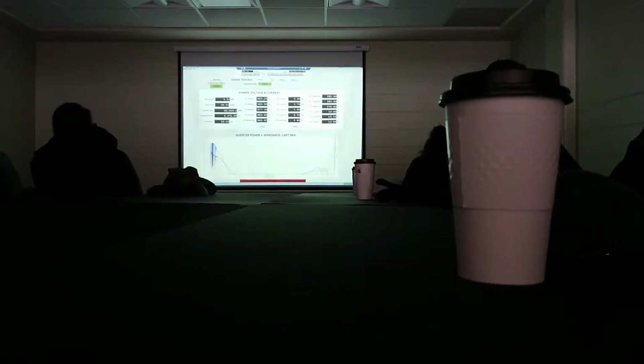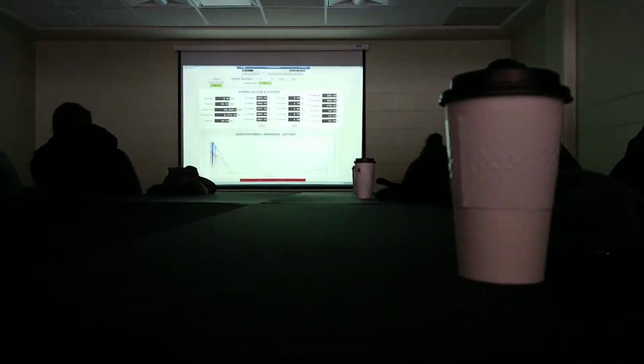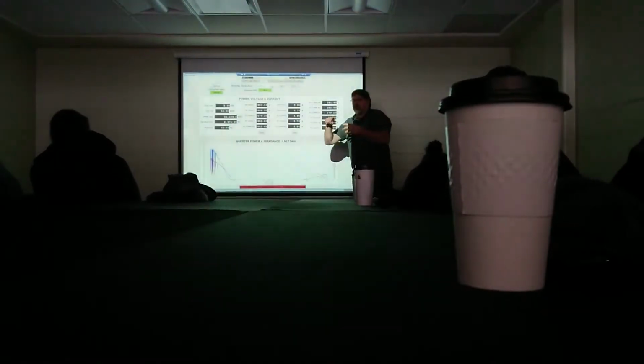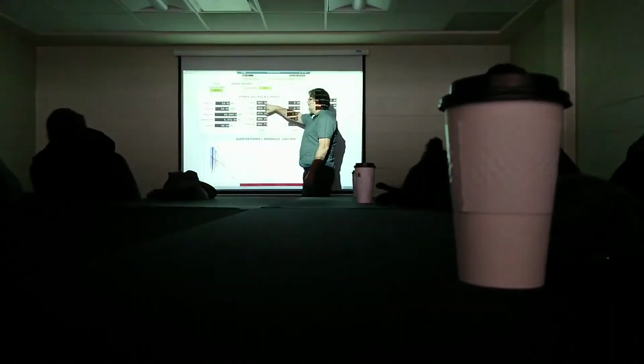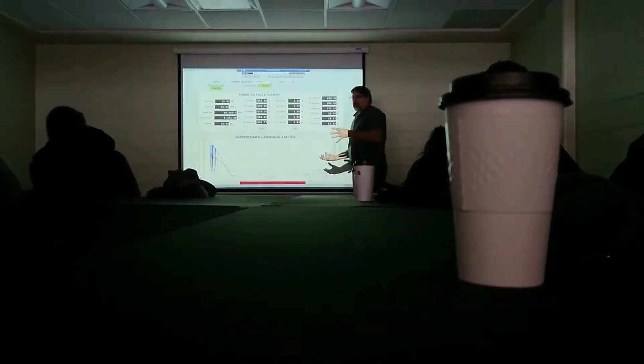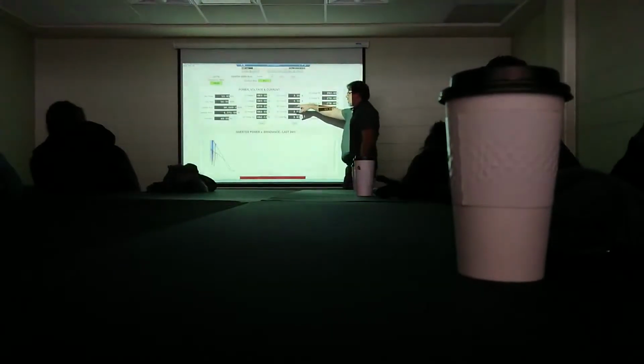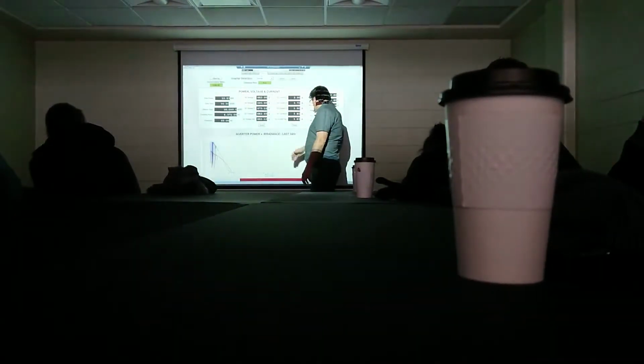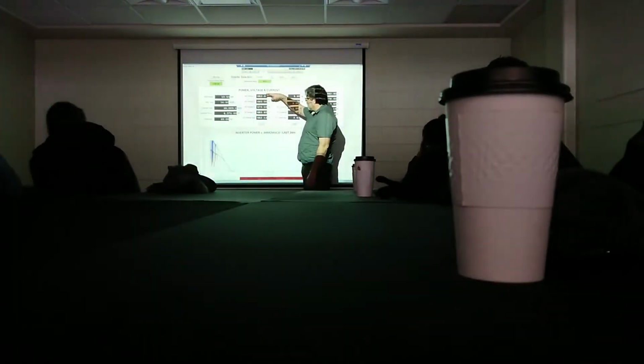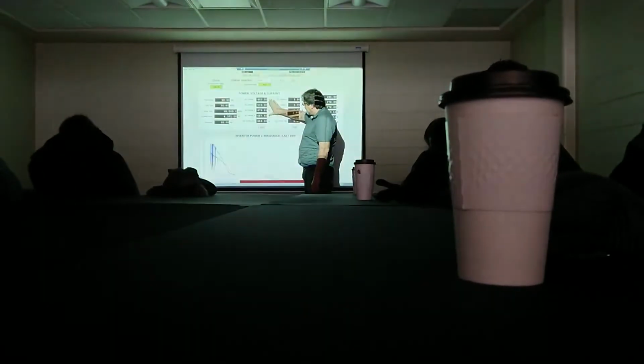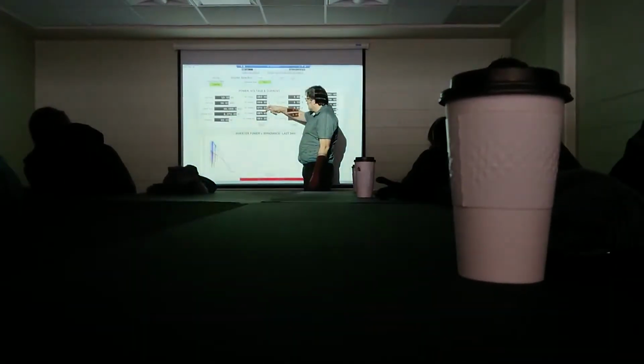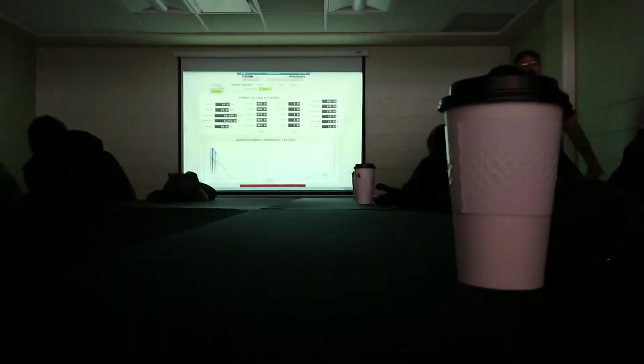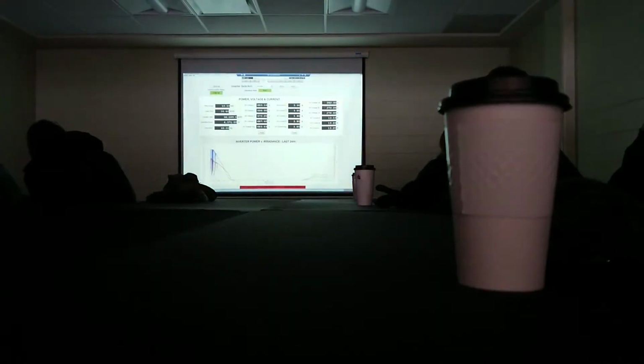They have 4 strings for each inverter, and each string goes up to 1,000 volts on a nice bright sunny day. So we can tell that since this isn't at 1,000 volts, we're getting less power than normal. But the nice thing is you can look at the 4 of them, and right now they look close in range, but when we click on that trend, one of them looks quite different from the others, so we'll go back into it again.